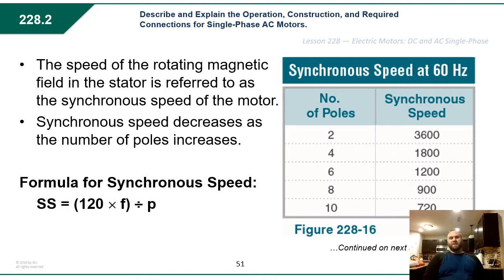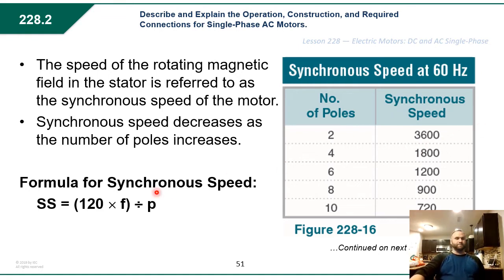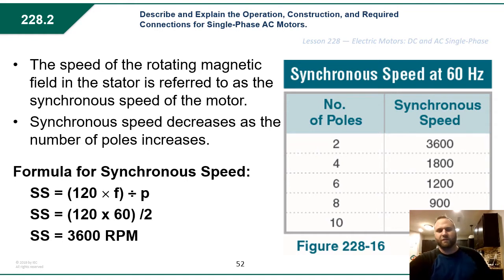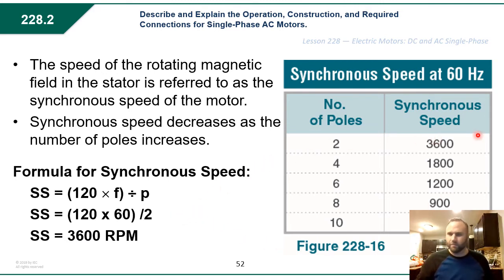The speed of the rotating magnetic field in the stator is referred to as the synchronous speed of the motor. Synchronous speed decreases as the number of poles increases — a two-pole motor has a synchronous speed of 3,600 RPM, whereas a ten-pole motor has a synchronous speed of 720 RPM. The formula for determining synchronous speed is: SS = 120 × frequency ÷ number of poles. For a two-pole motor at 60 Hz: 120 × 60 ÷ 2 = 3,600 RPM.